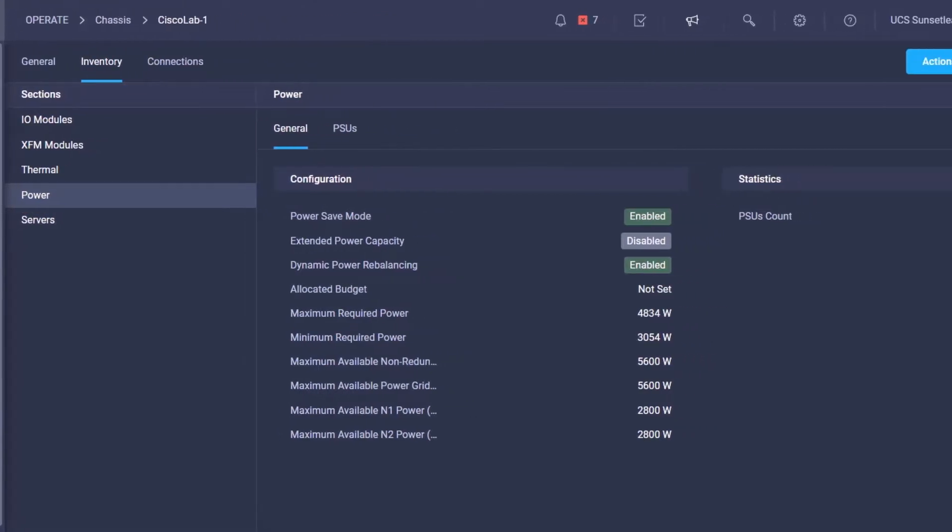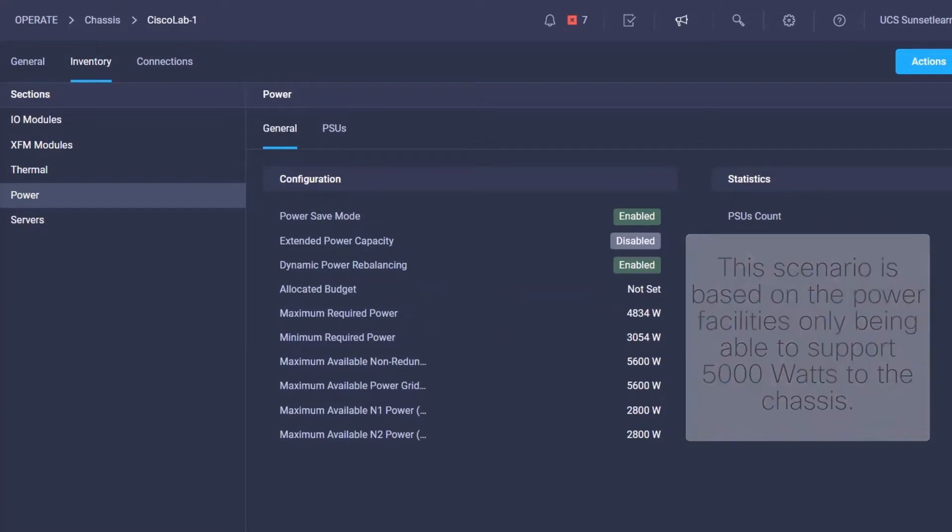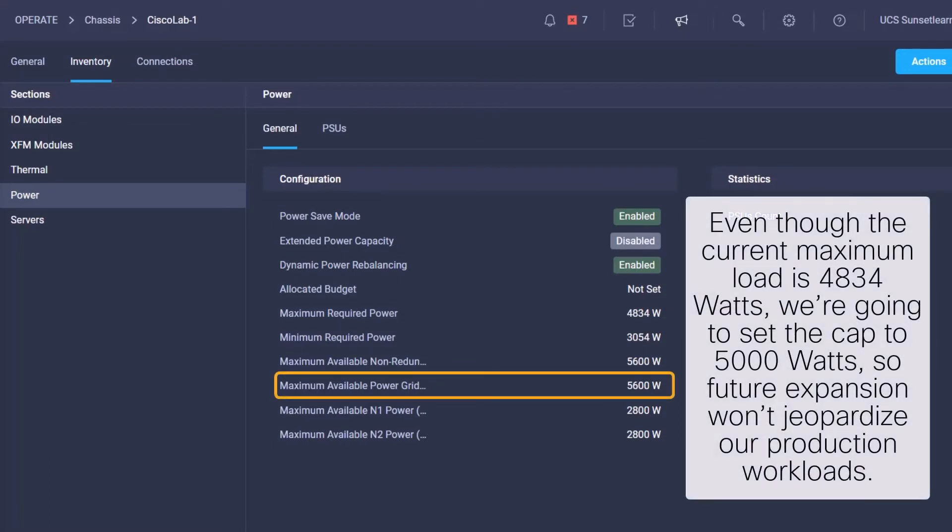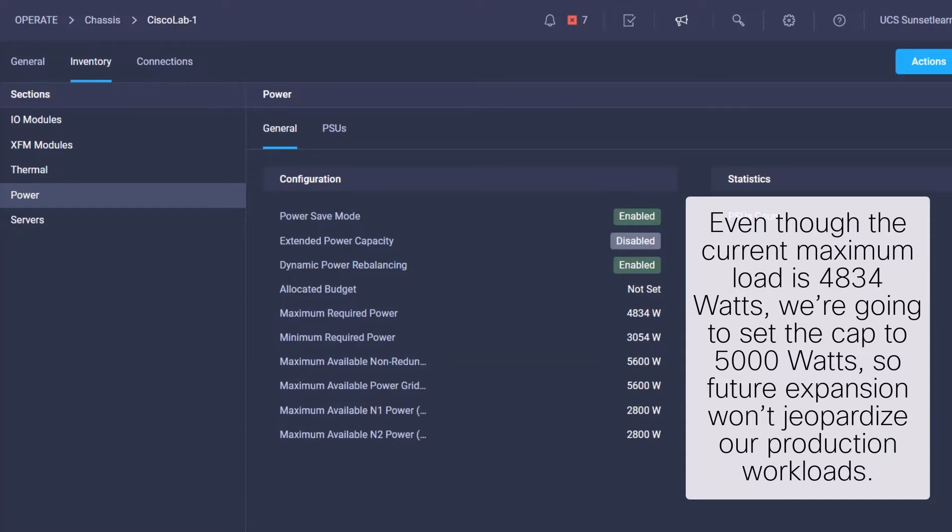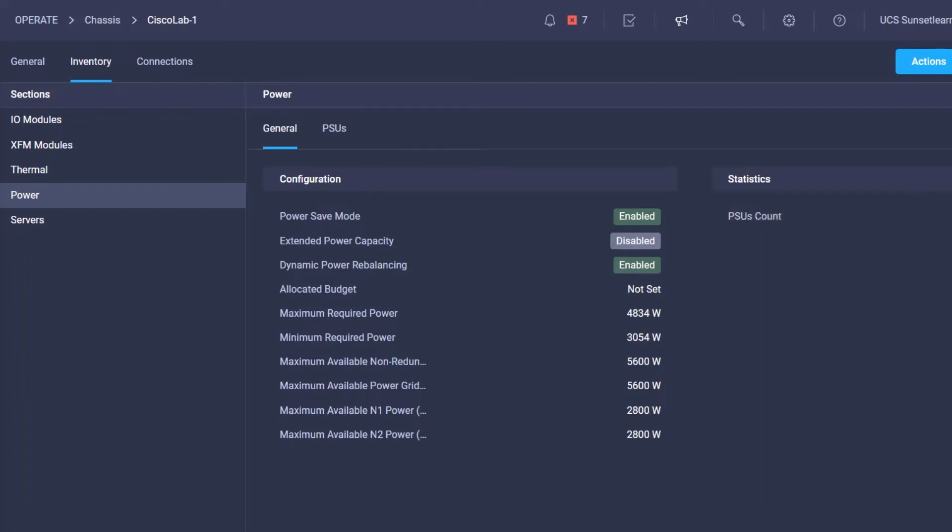Here we can see the max required power for our two servers is 4834 watts. The available max power is 5600 watts. So what we'll need to do is lower that power cap to something like 5000 watts so that we don't oversubscribe the available 5600 watts.